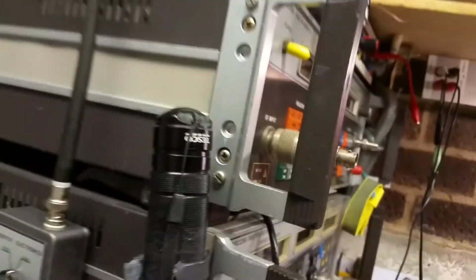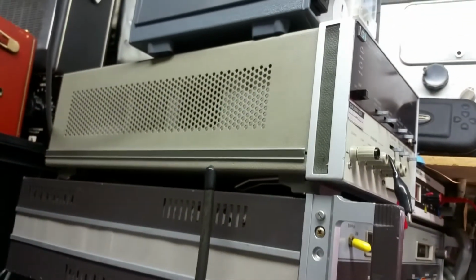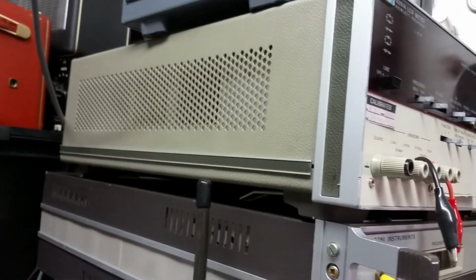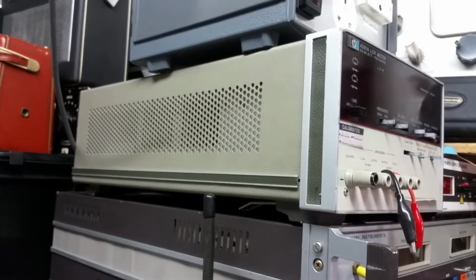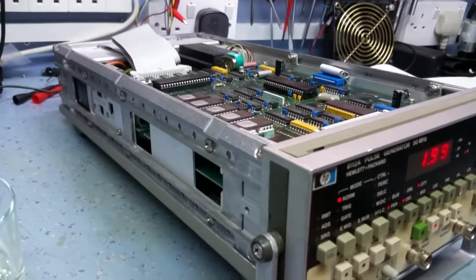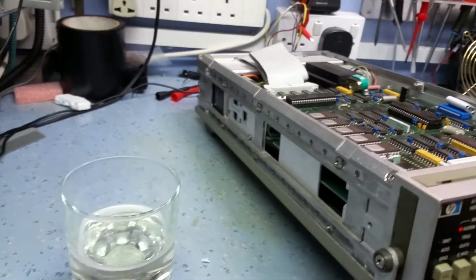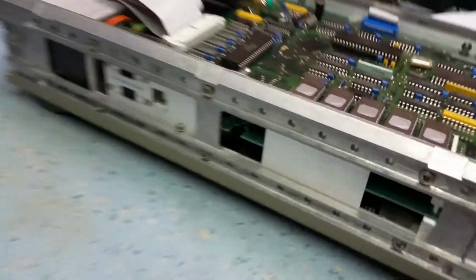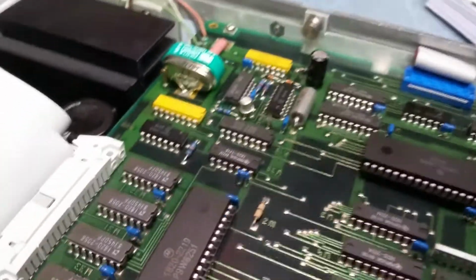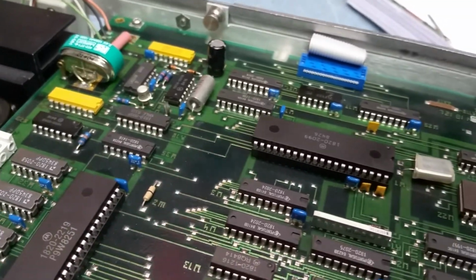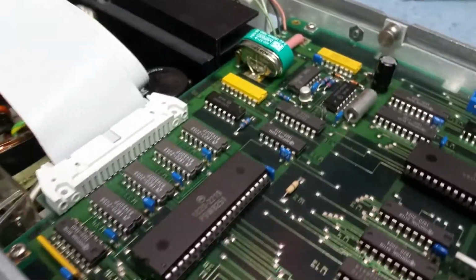It's much longer than the, look at the 4261 LCR. It's probably about another 6 inches longer than that. It's pretty hard to tell here, but it's certainly working okay. The battery is in good condition. That's a rechargeable lithium, so that's working fine. Check the power supply. First thing you do before you do anything is they tell you to check the power supply. The power supply ripple noise is well within spec, and the voltages were absolutely spot on. So that's a testament to the quality of the HP stuff.